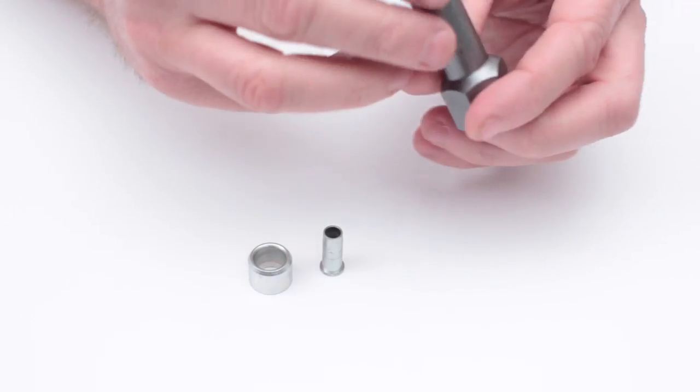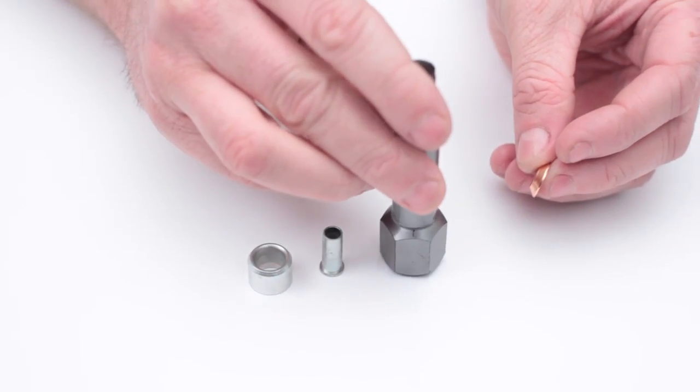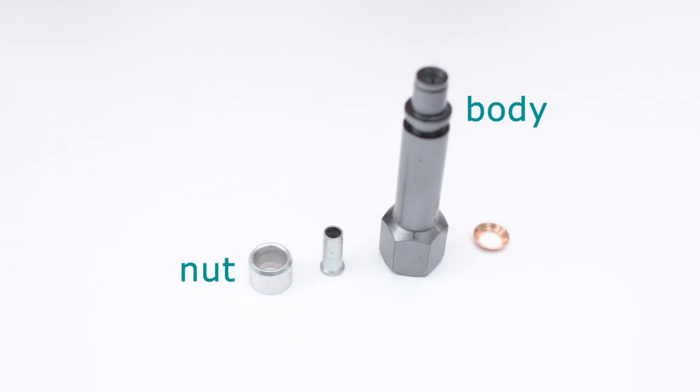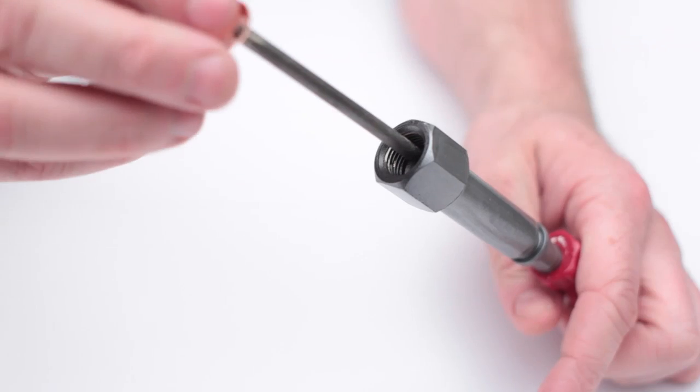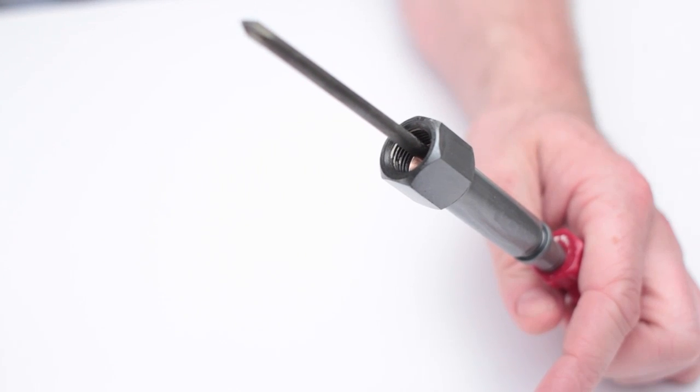The reflock fan coil connector consists of four components: the body, nut, insert, and copper washer. To aid assembly of the joint, begin by inserting a crosshead type screwdriver through the body. Next, thread the screwdriver through the copper washer with the dished side facing out.